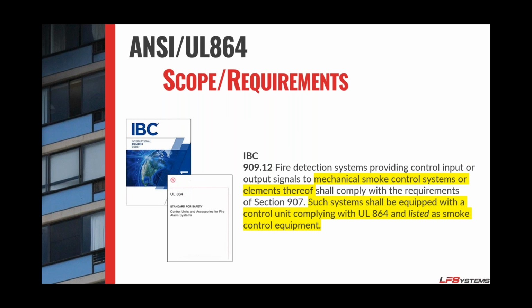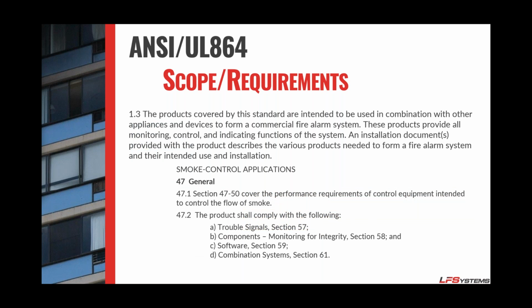Well, IBC 909 says any mechanical smoke control system or elements thereof shall be equipped with a control unit complying with UL 864 listed as smoke control equipment. So then we dig into UL 864, and I could read 4 chapters if you'd like. That'd be really fun and exciting on a Tuesday afternoon.